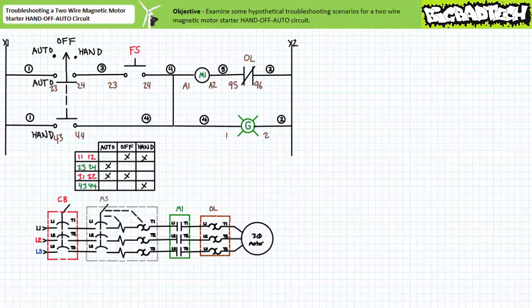All right, this about wraps up this brief application exercise. In conclusion, we examined some troubleshooting scenarios for the two-wire magnetic motor starter hand-off auto circuit. We examined the circuit's response to loss and restoration of power, overloads, malfunctioning automatic input, improperly wired input, the effects of opens in different areas of the circuit, and the effects of manual overrides.